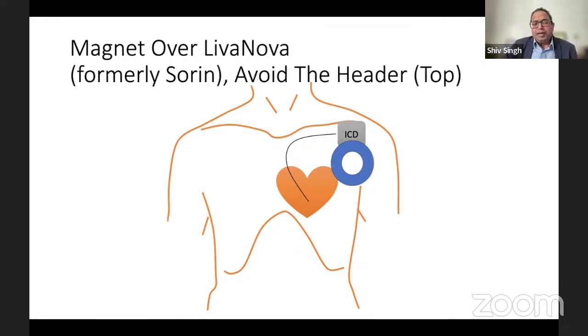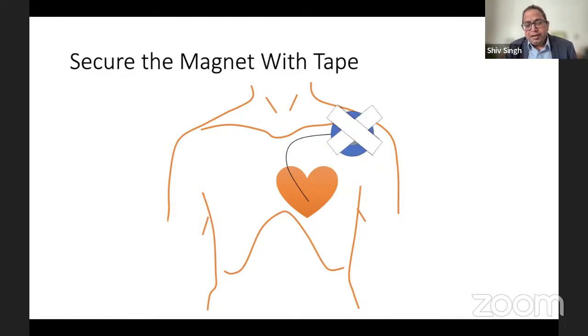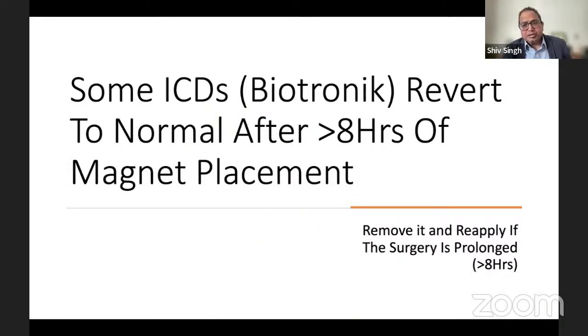Whereas if you look at LivaNova pacemakers, formerly known as Sorin, they were bought over by LivaNova, and it says that you avoid the header, the top end. It's always the bottom end, which has got the reed switch. So you apply it to the lower end of the pacemaker and it'll go into a fixed mode. If you need to use it throughout the operation, then you secure it with tape, because otherwise if you remove it, it goes back to its normal function. Some of the ICDs, like the Biotronik one, will revert back to normal after 8 hours despite the magnet being constantly kept on. So you take it off and reapply it again, and then you can use it for more than 8 hours.